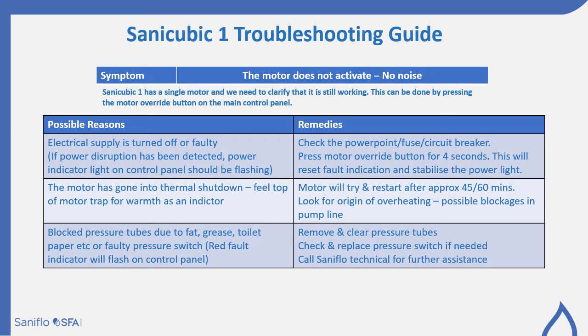It's possible the motor may have gone into a thermal shutdown. It's overheated, and when it does that, it just goes into a shutdown mode. So feel the top of the motor as an indicator for heat. If you find it there, then it's quite possible it's gone into a thermal overload. The motor will automatically try to restart after about 45 to 60 minutes, but it's important to look for the origin of the overheating. Possible blockages in pump lines could be a cause.